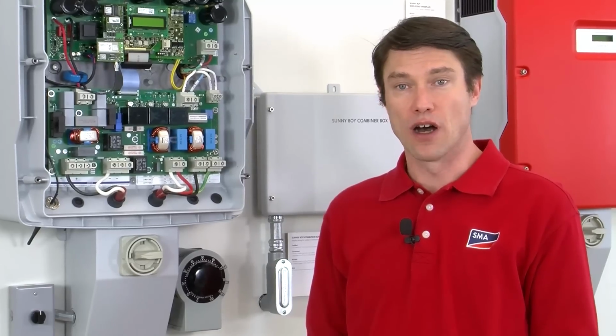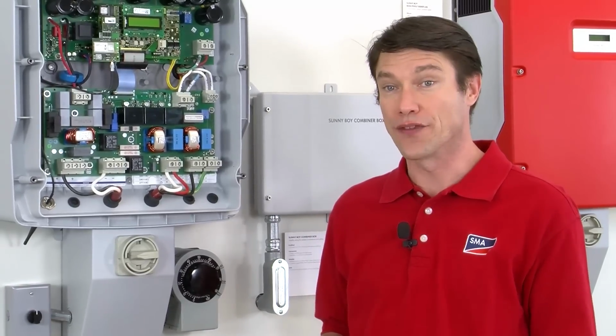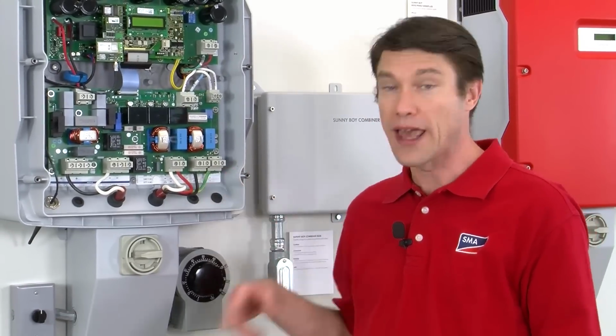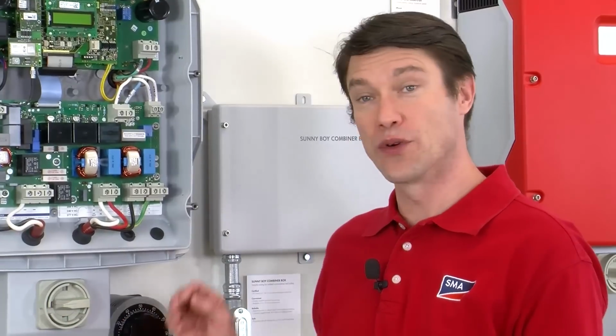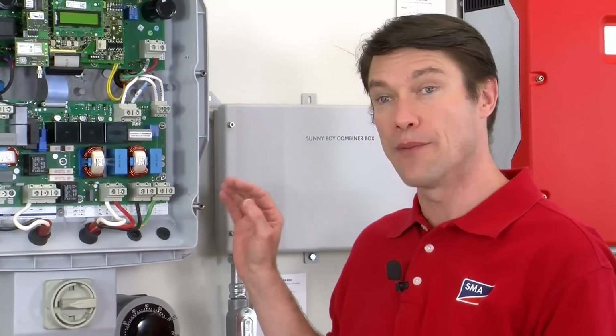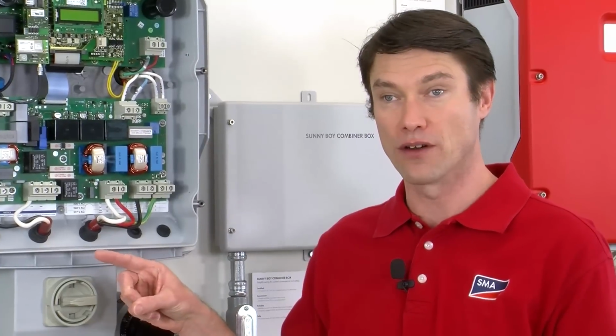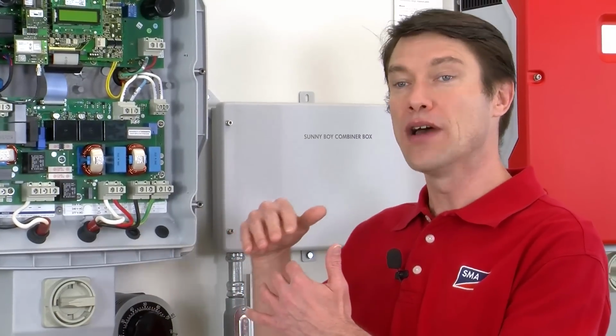Now, the next common cause is insufficient wire size on the AC run between the inverter and the utility panel. So if the resistance of that wire run is too high between the inverter and the utility panel, again, the inverter will have to have its output voltage be high enough to overcome that drop and still be at the voltage for the utility.